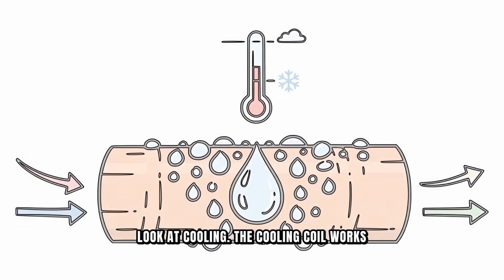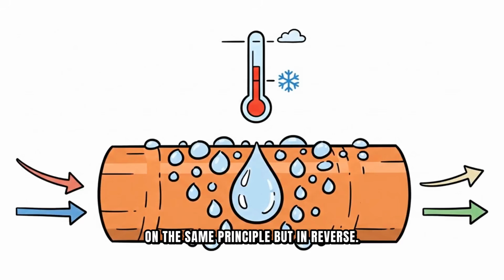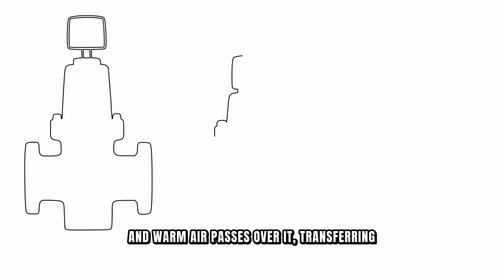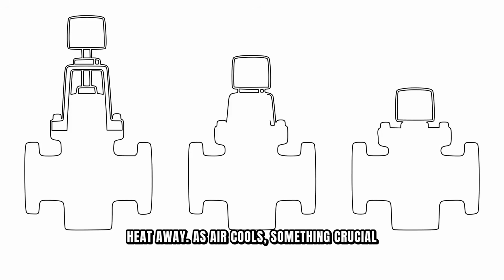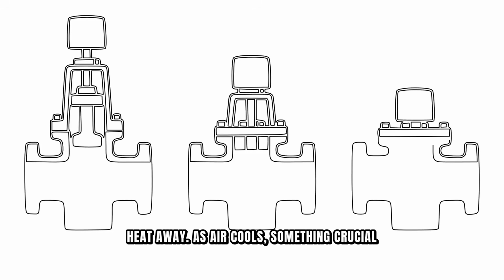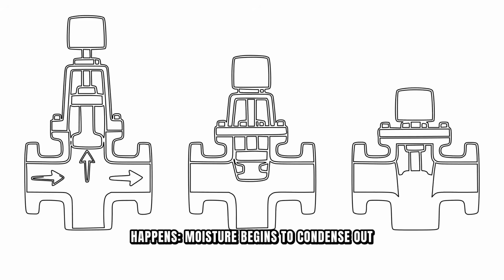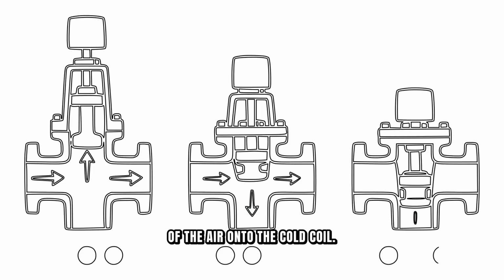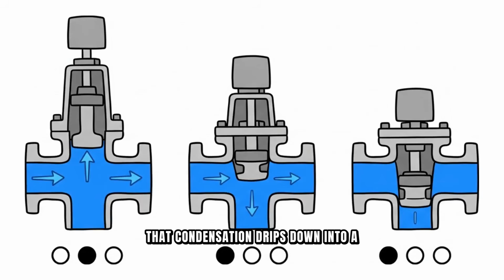The cooling coil works on the same principle, but in reverse. Chilled water from your building's chiller flows through the coil, and warm air passes over it, transferring heat away. As air cools, something crucial happens. Moisture begins to condense out of the air onto the cold coil. That condensation drips down into a drainage pan beneath the coil and exits through a drain line.